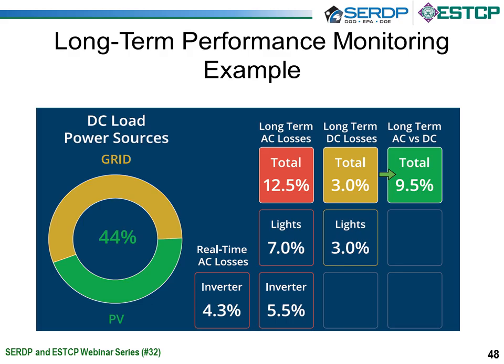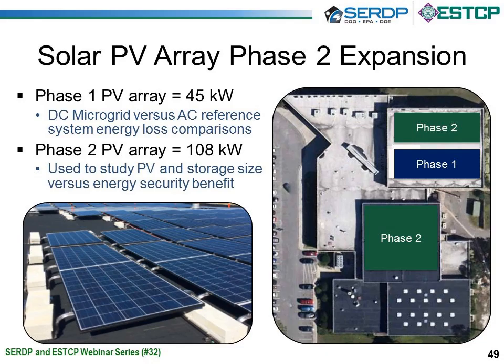And it's interesting, the inverter actually loses more power in the wintertime, which we'd expect because it's operating more at its lower power levels. So the DC system outperforms the AC system more in wintertime, less in summertime. But again, we've modeled across the entire year that we would have about a 7 to 10% improvement in any climate within the U.S. for a DC system.